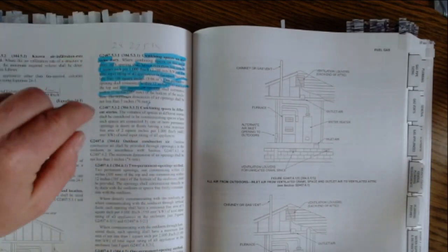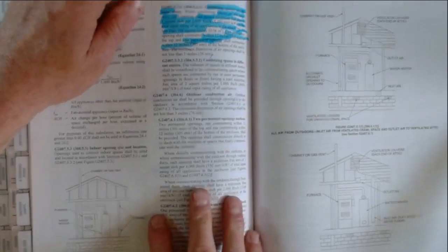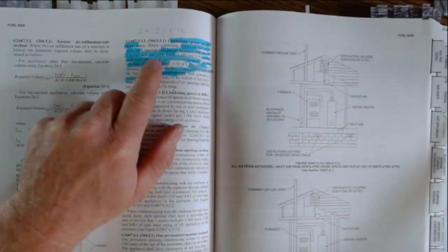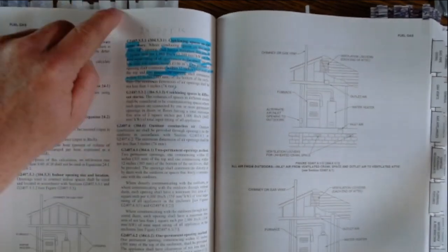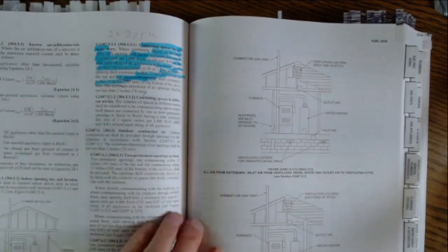but it's top and bottom. Okay? So let's say a minimum 10-inch by 10-inch opening at the top of a room. We're talking rooms here, okay? You have openings top and bottom. It's minimum 10 by 10 here, 10 by 10 here. Even though it says 1 square inch per 1,000 BTU, it's actually 2 square inches per 1,000 BTU because 1 square inch is at the top, 1's at the bottom. That's what these mean. It'll always get you in a test. You got to know that's double. It's actually double what it is.